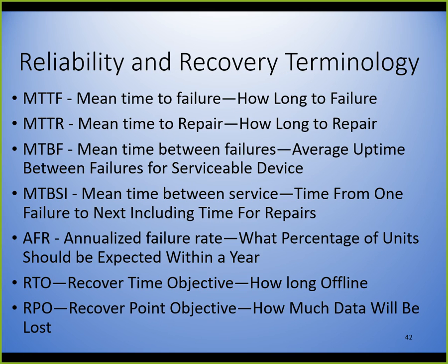Some terms here, a whole bunch of terms. There are a lot of terms in the disaster recovery. MTTF is a mean time to failure. How long is it going to be before it's going to fail? And this is based on historic evidence, obviously. And MTTR is mean time to repair. How long is it going to take to fix it? MTBF, mean time between failures. The average uptime between failures for a serviceable device.